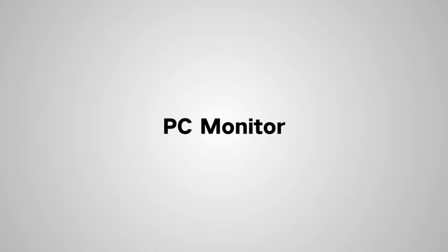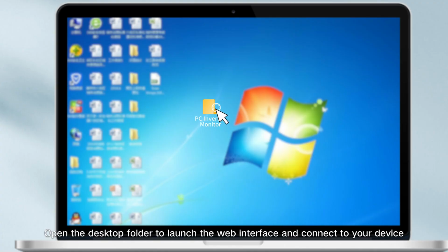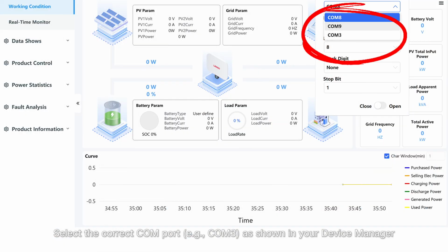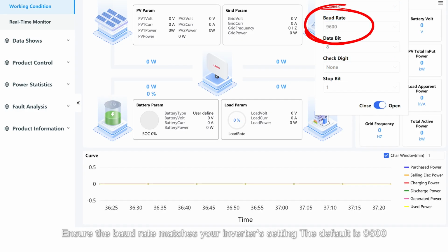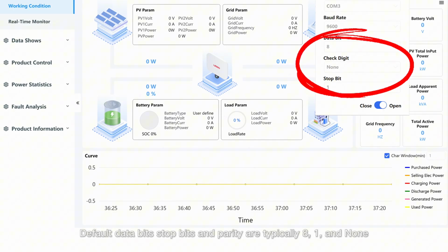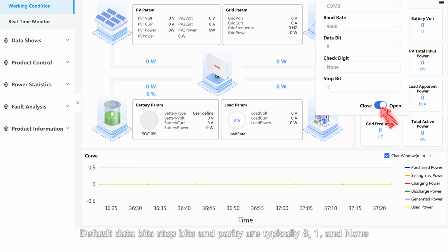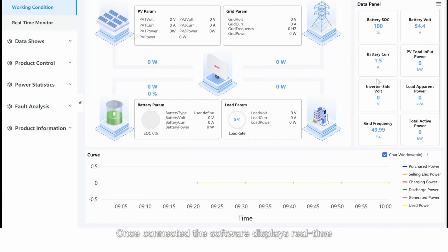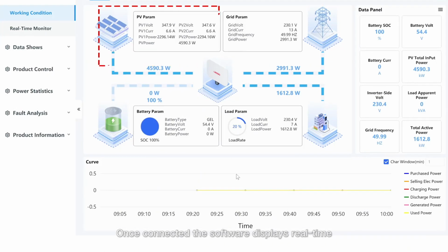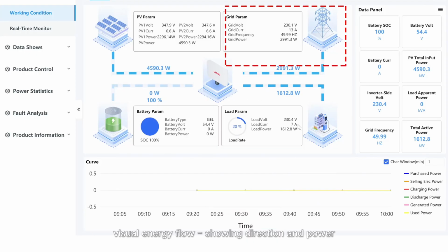PC Monitor. Open the desktop folder to launch the web interface and connect to your device. Select the correct COM port, for example COM3, as shown in your device manager. Ensure the baud rate matches your inverter setting. The default is 9600. Default data bits, stop bits, and parity are typically 8, 1, and none. Once connected, the software displays real-time, visual energy flow, showing direction and power.